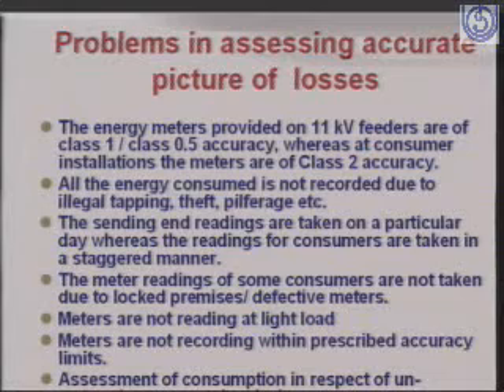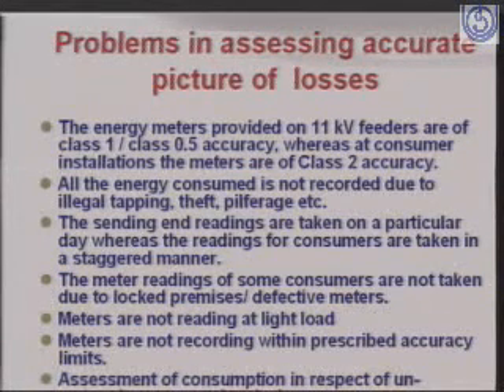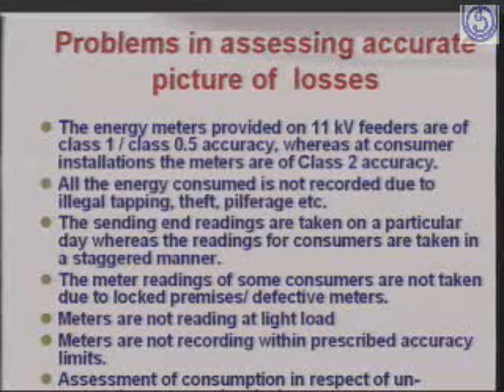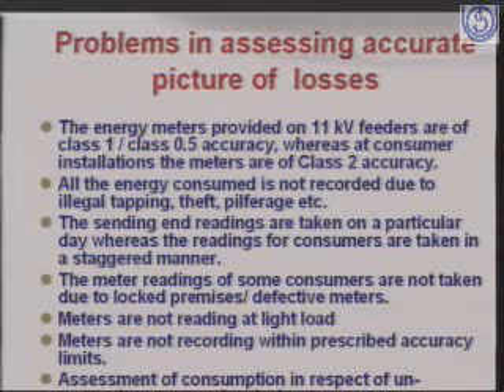There are problems in assessing such an accurate picture of losses. Basically, these problems relate to technical areas. We have energy meters which are provided on 11 kV feeders which are of class 1 or class 0.5 accuracy, whereas at the consumer end we have meters of class 2 accuracy. So there is a mismatch here.